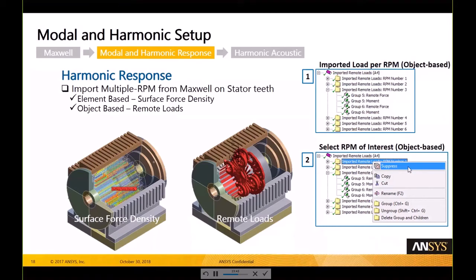The comments made earlier were related to a single RPM for a single given speed. We can perform a discrete Fourier transformation on electromagnetic transient forces, either element-based or object-based, and transfer these frequency domain forces into harmonic response. For multiple RPM, we calculate multiple speeds as multiple design points within magnetic transient simulation, and we perform discrete Fourier transformation the same way for every single speed considered.